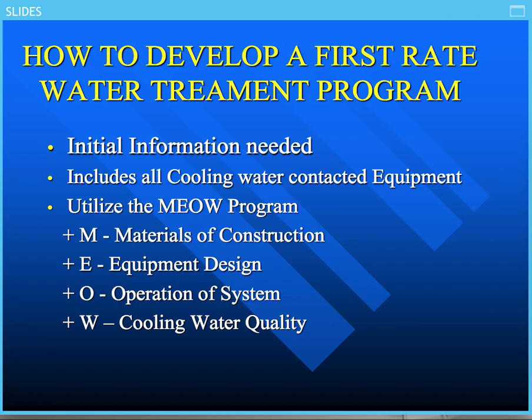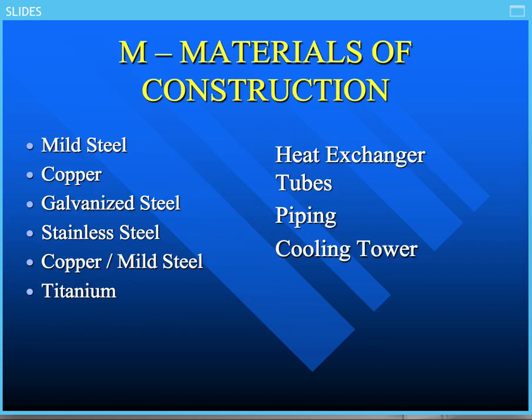The M stands for the materials of construction that are contacted by the cooling water itself. The E stands for the equipment design. The operation of the system is what the O stands for. And last but not least, we're dealing with what the cooling water quality is. So these are the things that we have to look at. Next slide, please.